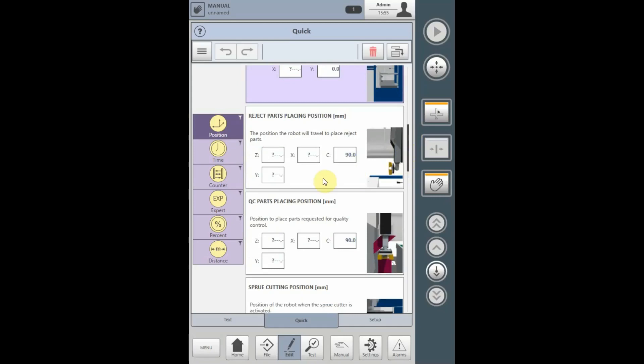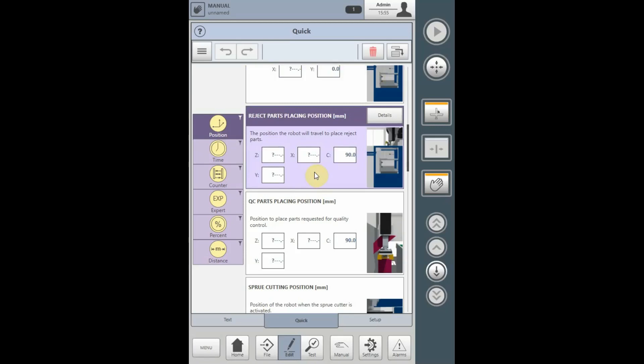The reject parts position will be available if the selection in the interview process for the reject sequence was selected as yes. The reject parts placing position will be the location the robot goes to if a startup reject was selected or a machine reject signal was given. All parts and runners will be dropped at this location.